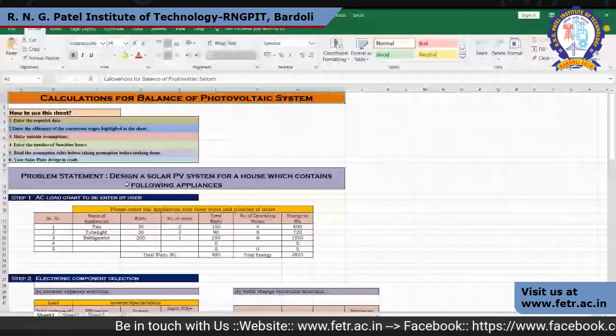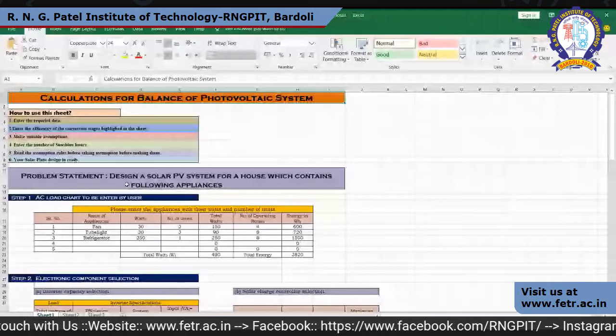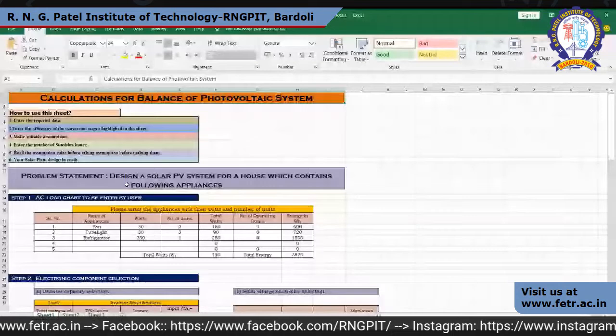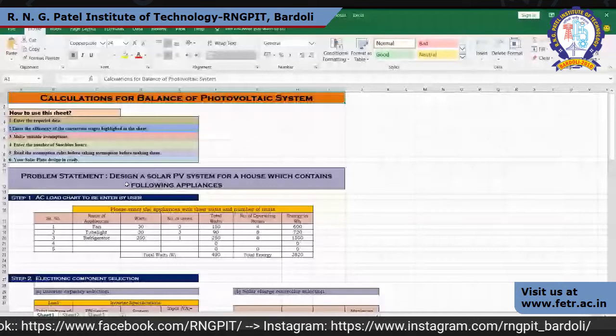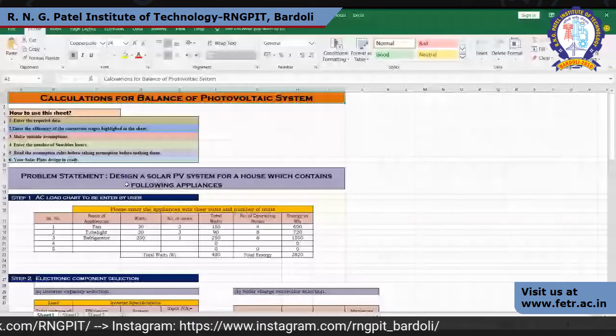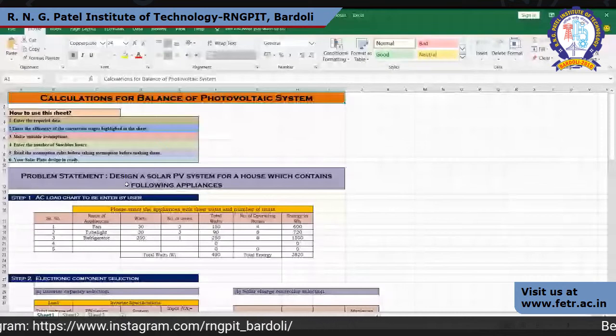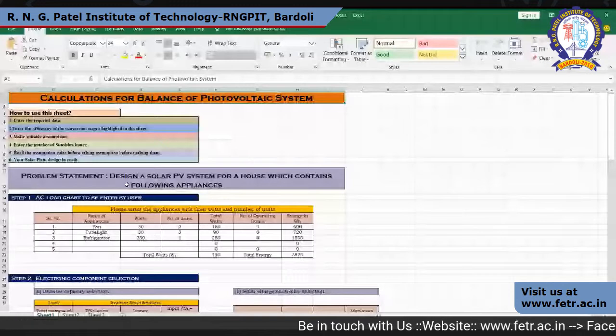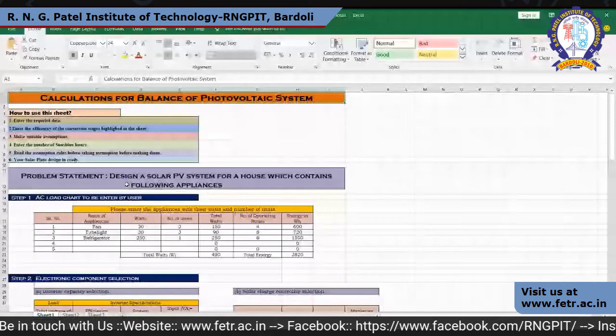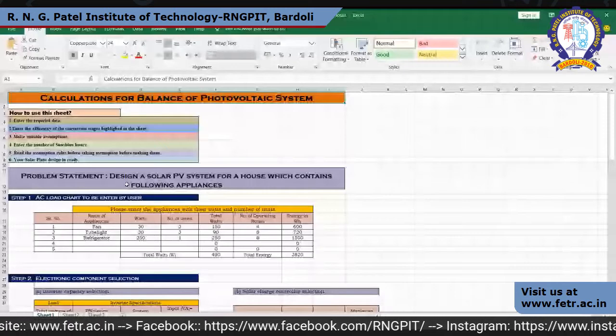We are assuming the worst data for the best design. Anyhow, you can assume 90% or 95% also. In this case, we'll assume 70%, and according to that, your actual ampere hour will be there. This ampere hour is of the battery. Obviously, in the market, a 183 ampere battery is not available, but the nearest value, 200 Ah, you can take.